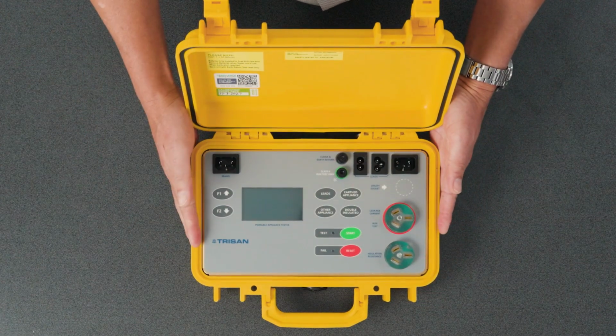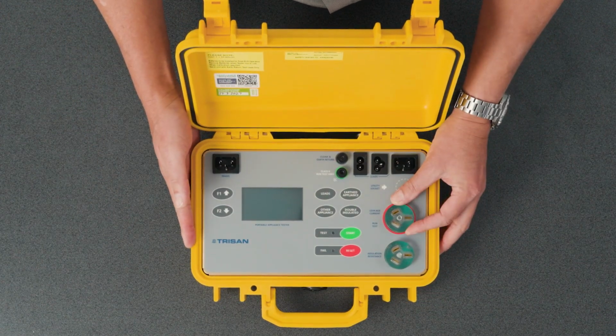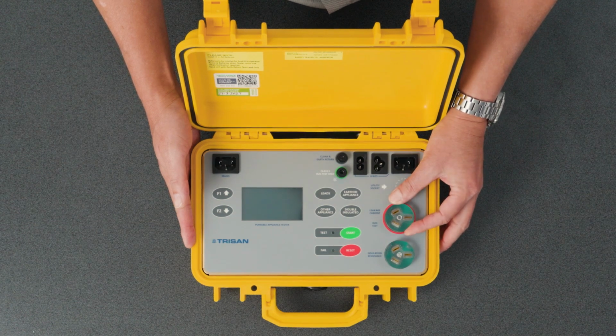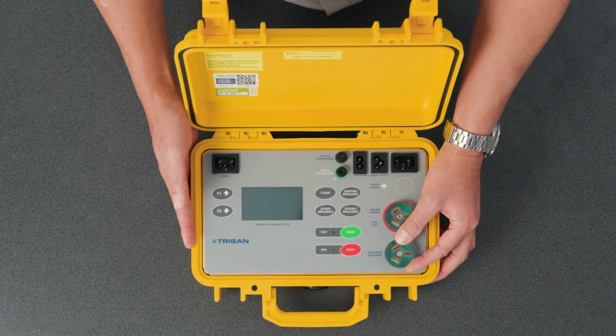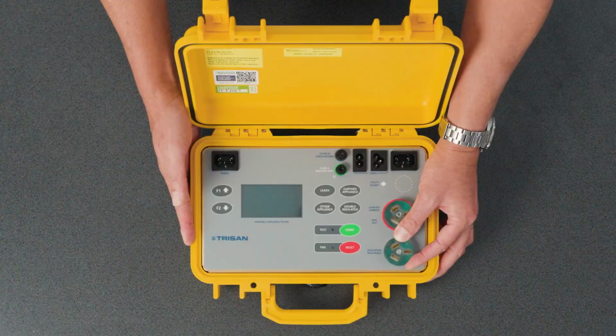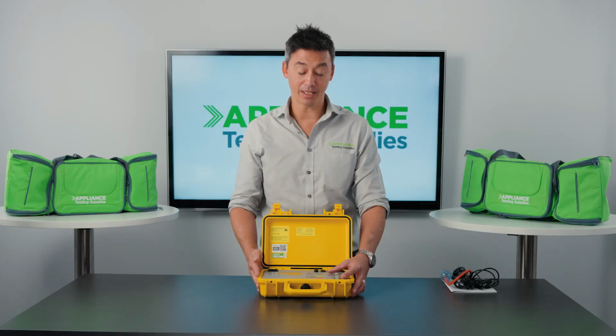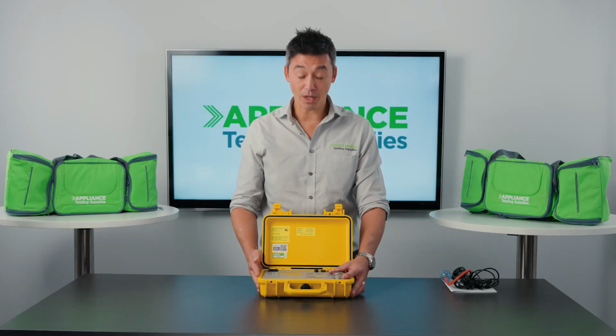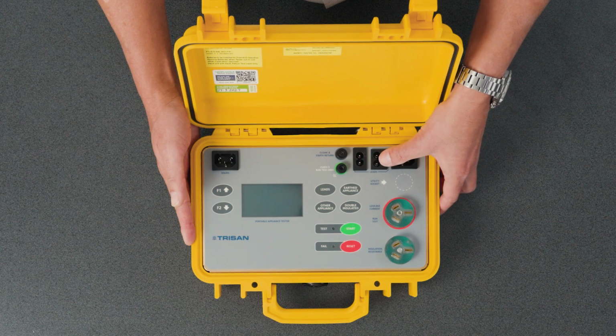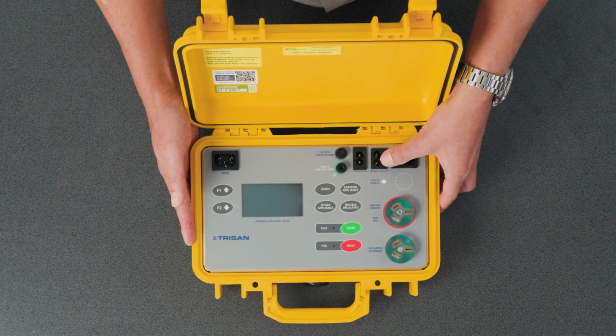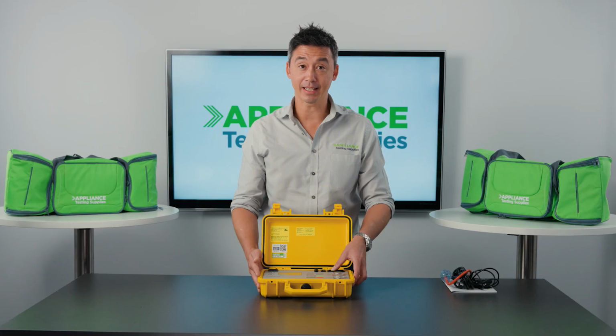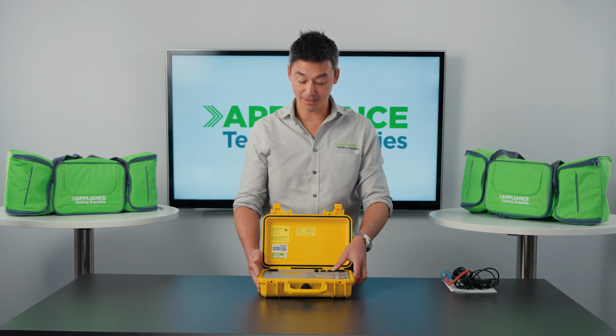So first things you will notice with this device, it does have two test sockets here, one for doing leakage current testing and the other for doing standard insulation and earth continuity testing. Now this is built for safety, but it's very unique with this particular brand. What you'll also notice is that it does have a cloverleaf and a figure 8 connection here so that you can test those particular leads without using special adapters.